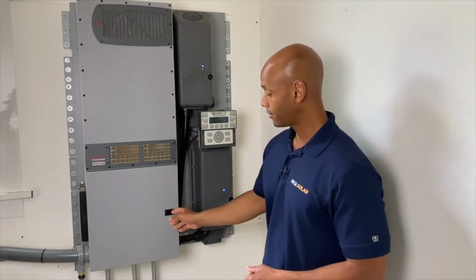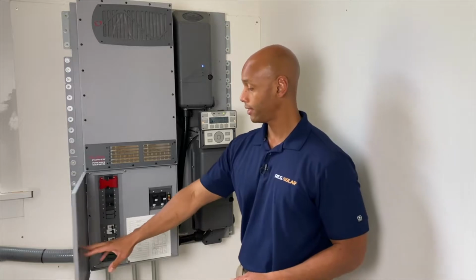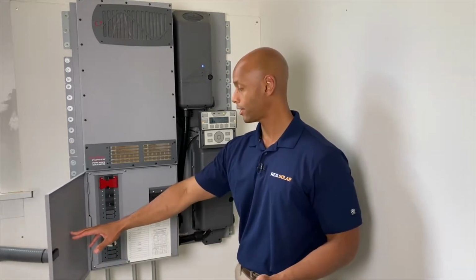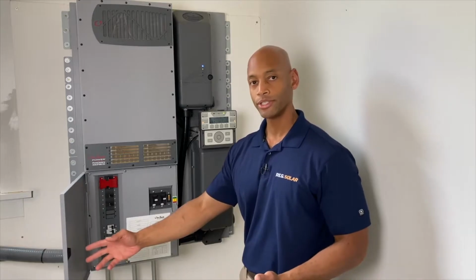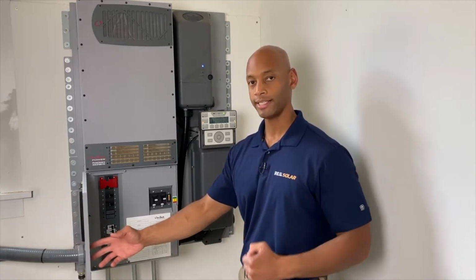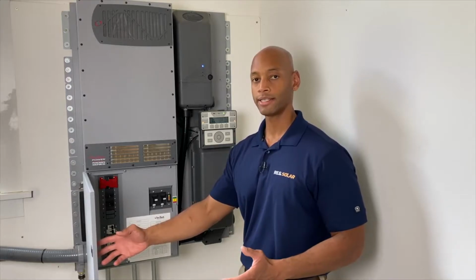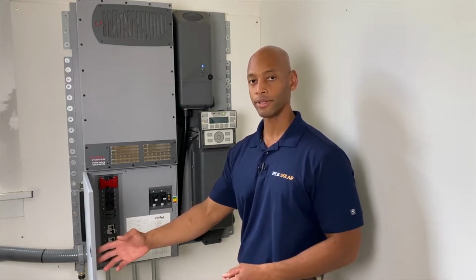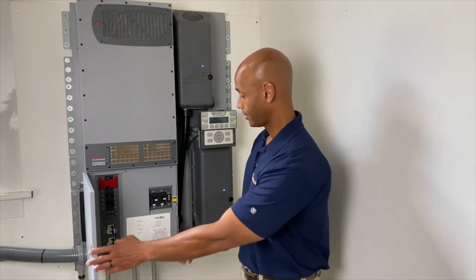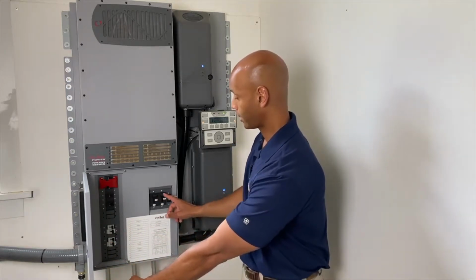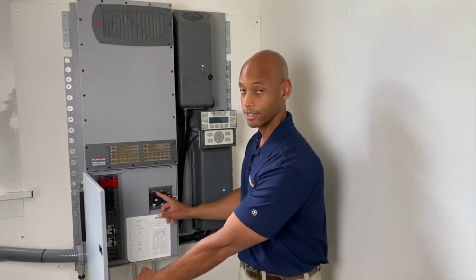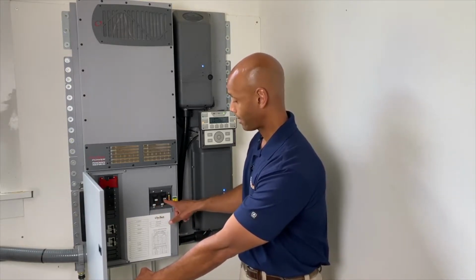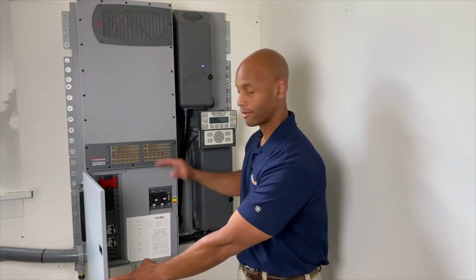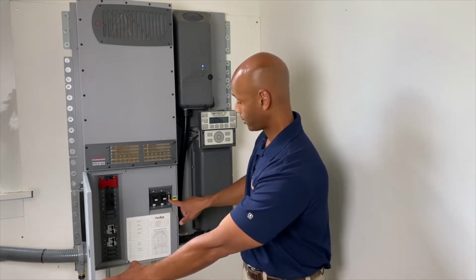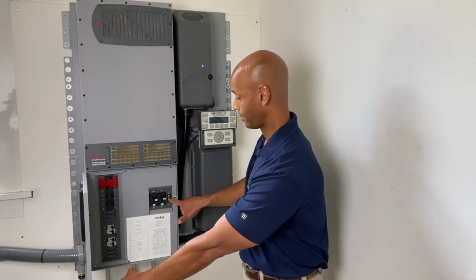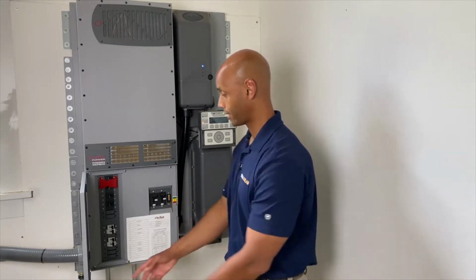All right. Underneath the inverter is your load center, and this is where you have all your switch gear. When we talk about switch gear, it's usually a circuit breaker or a disconnect switch. It's a means of disconnecting or isolating each of the individual components. Here you've got two large circuit breakers. These are your battery connection to the inverter. They're 175 amps each, and if we had to cut battery power to the unit, we cut these off here. You'll also notice there's a battery charge indicator light just to the right of those circuit breakers.